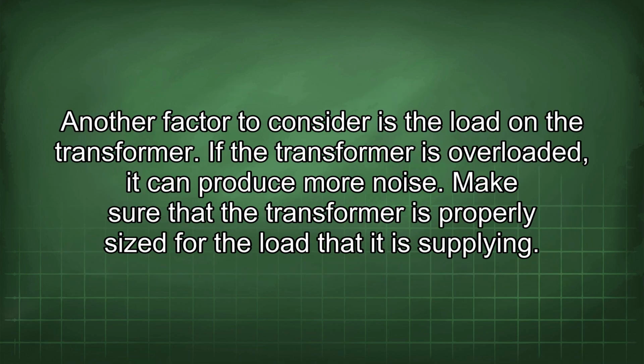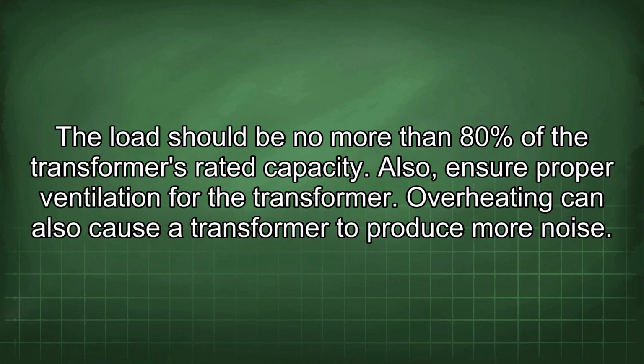Another factor to consider is the load on the transformer. If the transformer is overloaded, it can produce more noise. Make sure that the transformer is properly sized for the load that it is supplying. The load should be no more than 80% of the transformer's rated capacity. Also, ensure proper ventilation for the transformer. Overheating can also cause the transformer to produce more noise.